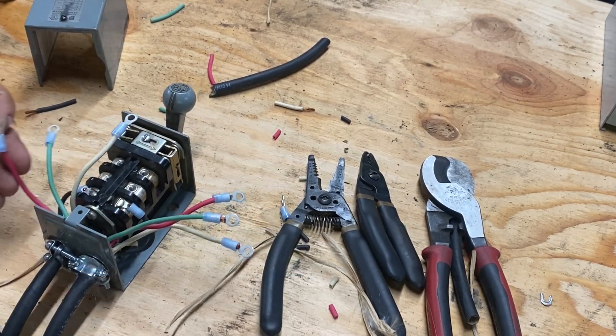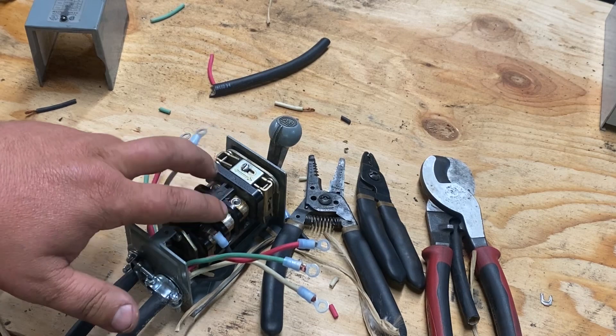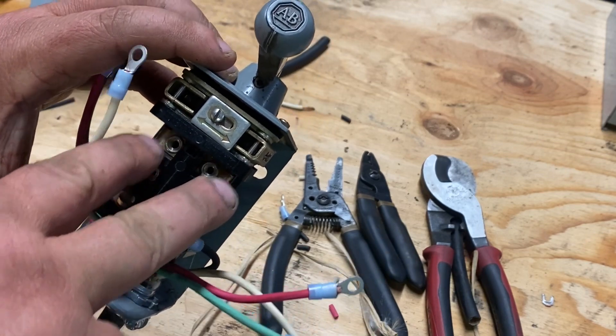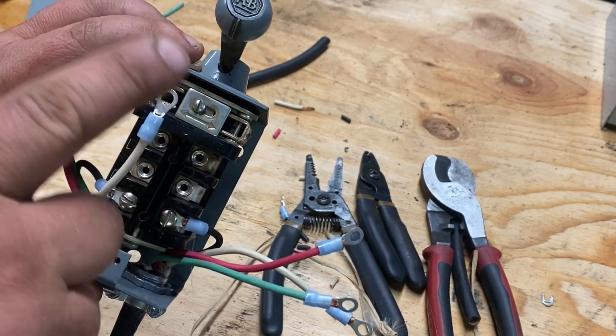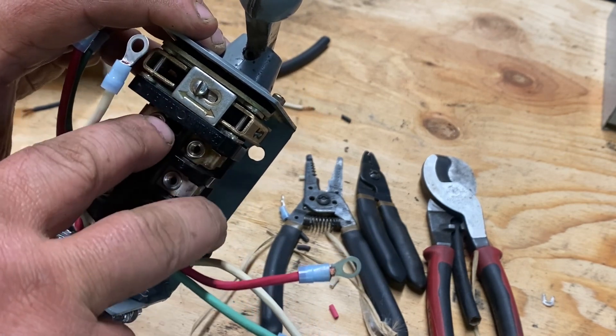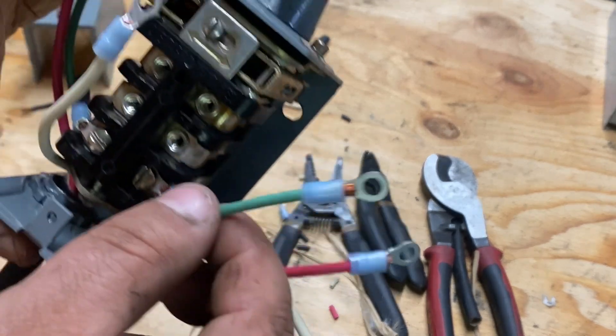My incoming other two power wires will be opposite each other diagonally, so they can never see each other. When the switch is flipped one way, power goes up and down; the other way it goes sideways across this specific switch. So if you put one hot wire there and the other one there, they can never see each other because they're either going that way or that way.